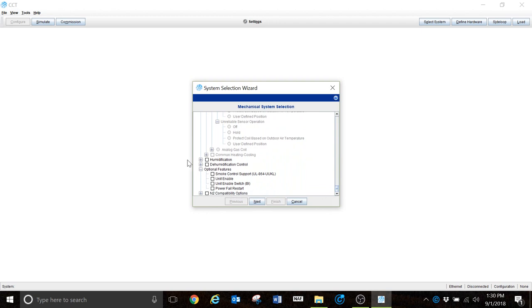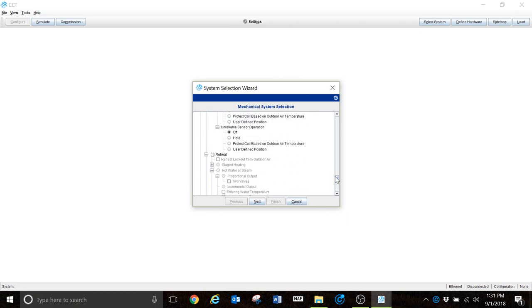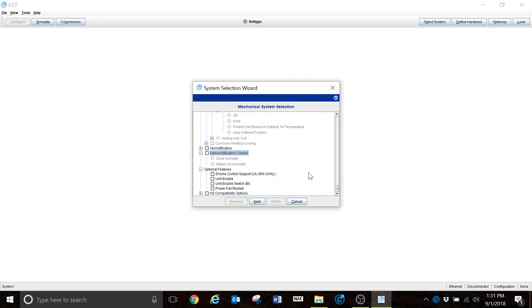Here is your dehumidification control sequence — if selected, we would be reading zone humidity. I will tell you a bad situation I have seen: people try to add dehumidification control after the fact without any type of reheat in the system. From personal experience, it does not work. If you want good dehumidification control you need coils after that chilled water coil to reheat that air — there is no way around it. You're fighting the laws of physics and you're not going to get effective dehumidification without some type of reheat, either through the VAVs or a reheat coil.